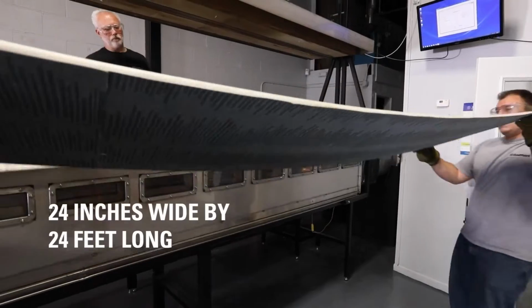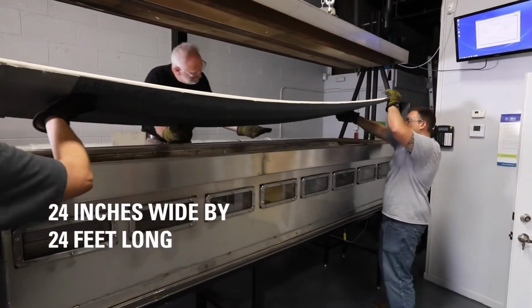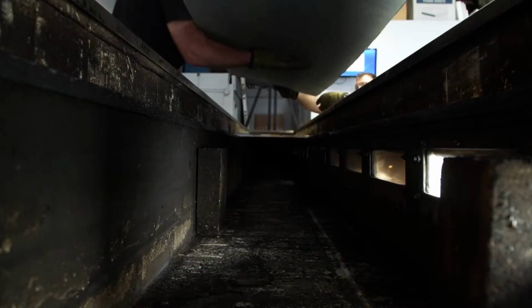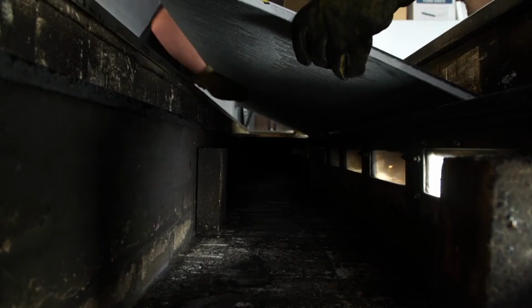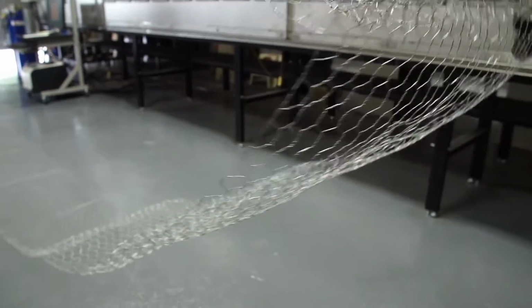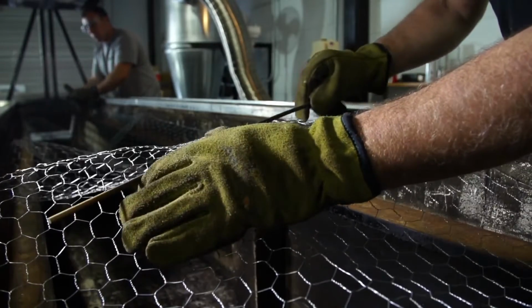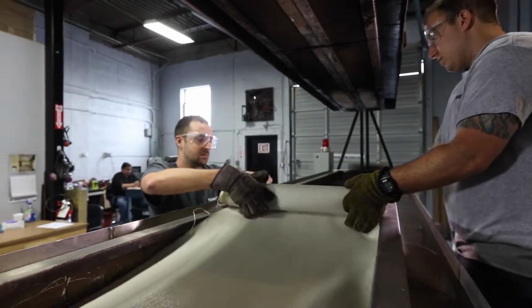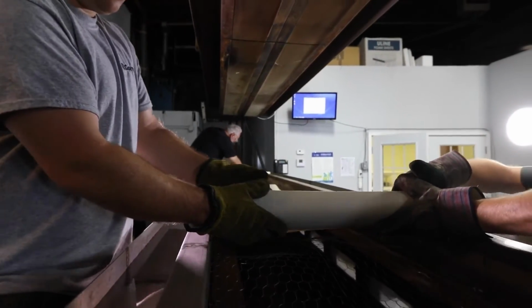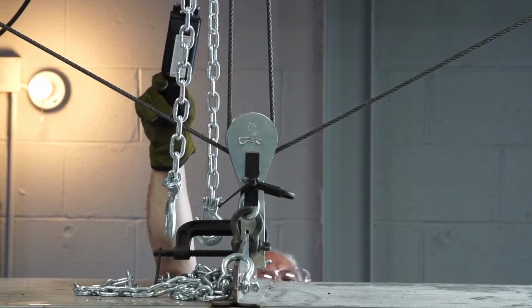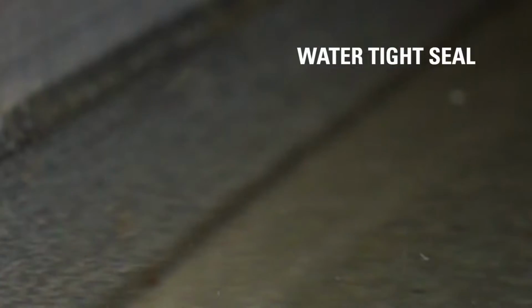The test specimen, measuring 24 inches wide by 24 feet long, is placed horizontally on the test chamber's inner ledges, facing down. Specimens that are not required to be mounted to a substrate are laid upon wire mesh and steel rods for support. Once the test materials are secured properly, the test chamber is closed with a watertight seal.